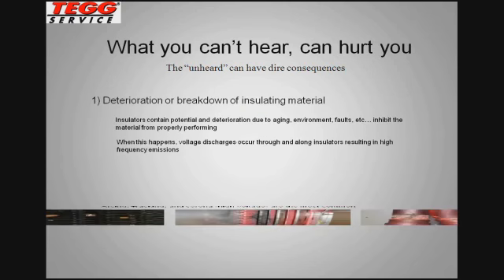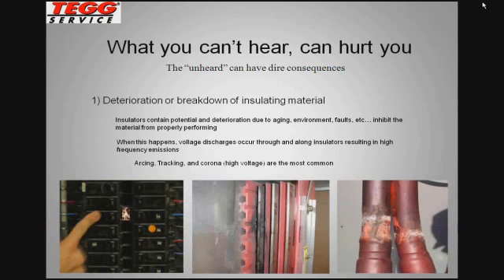Deterioration or breakdown of insulating material comes in several forms. And the bad thing about it is when it starts to deteriorate, it loses its ability to maintain or contain the potential within there, and it prevents it from performing properly. When this occurs and the insulation breaks down, you get discharges along those insulators or through them that are seeking a path to ground. And as these discharges occur, it creates the high-frequency emissions that we're detecting with the ultrasonic probe. So the most common ones found in electrical are arcing, tracking, and in high-voltage systems over 1,000 volts, corona.